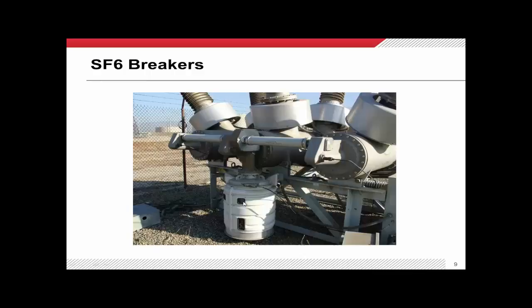This breaker is out of service and off to the side. Right here in this breaker is the spring. In any circuit breaker you have to have a stored energy mechanism. Most modern circuit breakers use a spring about 10 to 12 inches wide — a series of concave steel plates stacked alternately — with a big motor that charges it. As you charge it, it pulls down and flattens those steel plates, which can rebound and release that stored energy very quickly, in just a couple of milliseconds.